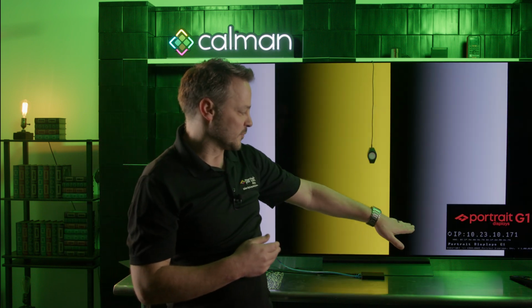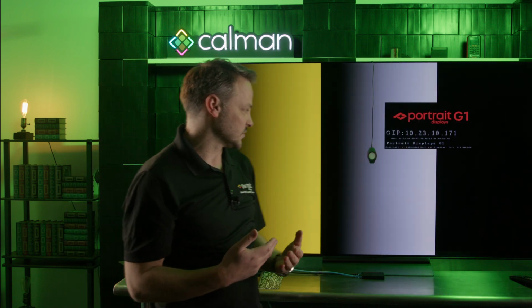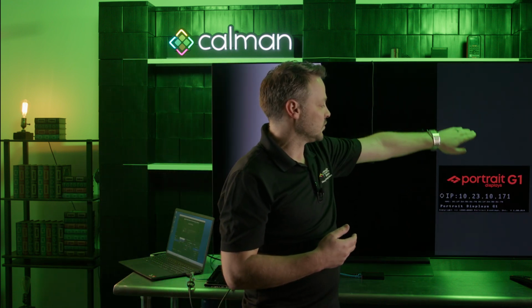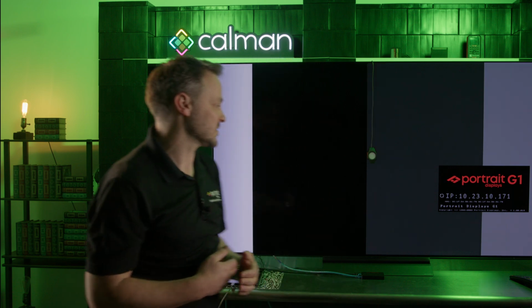Beyond that, we have some version information, so you know if the generator is in the current version or not. If it's not in the current version and it has a new update available, it will show that on this box as well. Once you connect to Calman, the next thing that the generator is going to do is put up an alignment pattern so that you can make sure that that meter is pretty close to the center of the screen. Again, it doesn't have to be perfectly centered. What's most important is that it is sitting flush against the screen, so there's no ambient light that's going to get in from the sides.